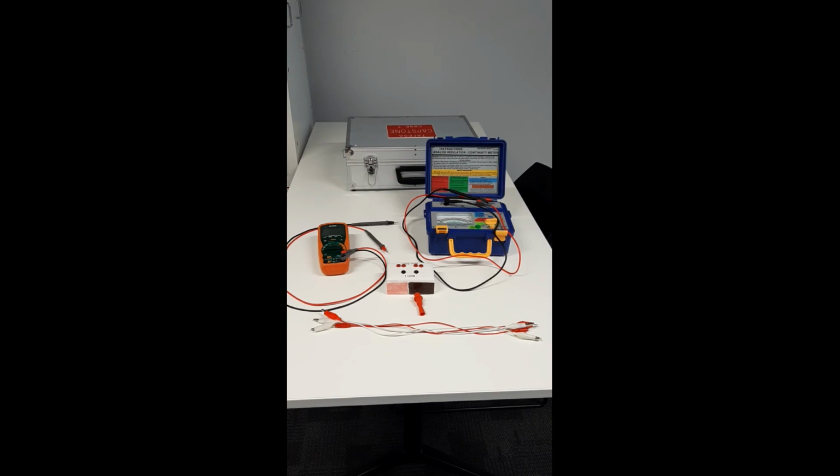The device and setting. To test insulation resistance, you need an insulation resistance tester. When selecting 500 volts DC, you are also selecting 200 megaohms device setup. Prior to testing, check the battery is okay, the testing leads, and place them in the correct terminals of the meter. Select the 500 volt DC.